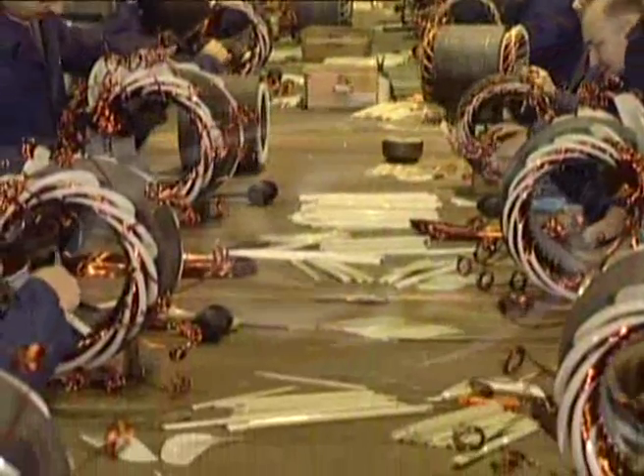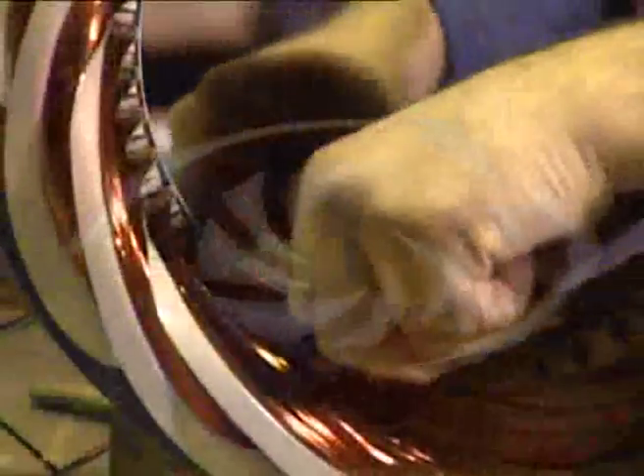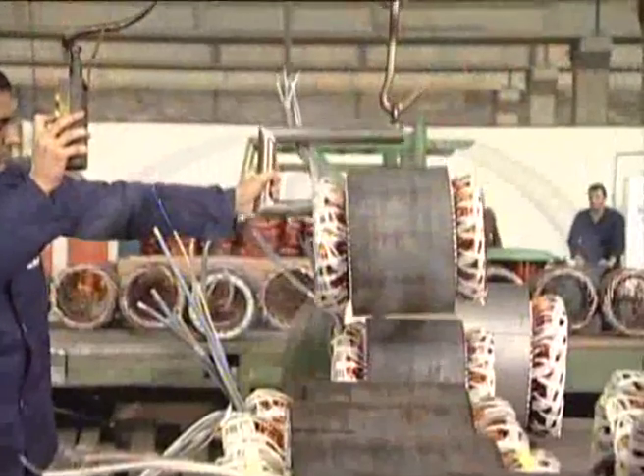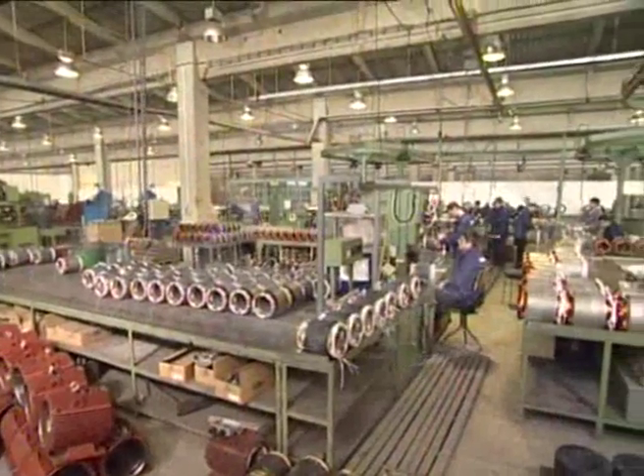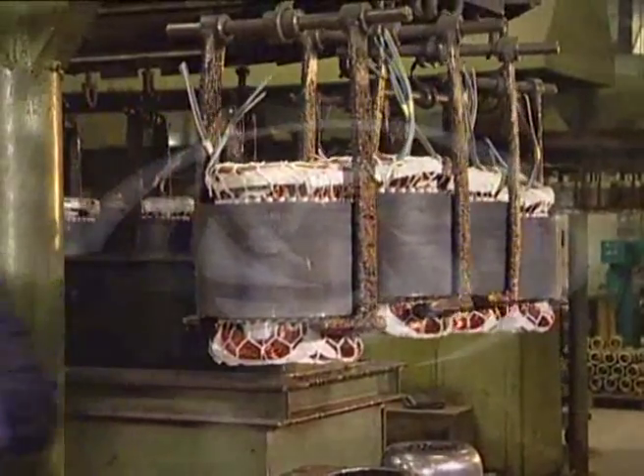Large motor and non-standard motor windings are wound at automatic winding machines and hand inserted to the stator slots. Leads are welded to the conductors and the stator is ready for testing. The windings are impregnated by dipping in Class H resin and then thoroughly baked to ensure high resistance to vibration.